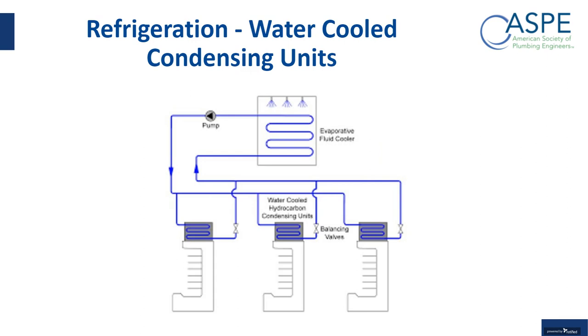And then next is refrigeration systems. So on the bottom here, we have 3 water-cooled condensing units, and then you have a pump that's flowing the coolant through all these systems, and you have balancing valves here. These could be manual balancing valves. They could be pressure independent balancing valves. They could be electric balancing valves. And then you have the evaporative fluid cooler, where you keep on cycling through this and it keeps on condensing and cooling off the water.